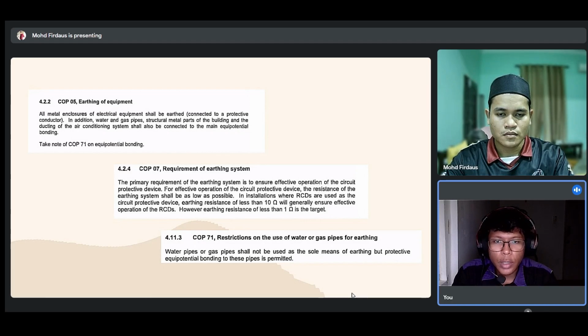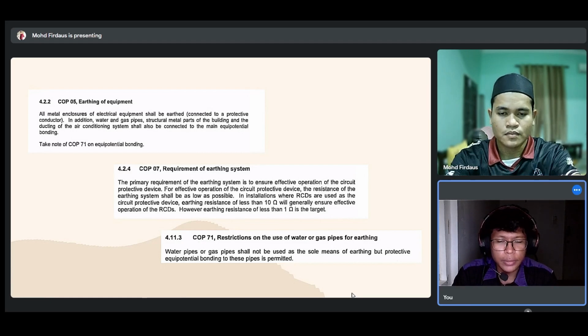In installations where RCDs are used as the circuit protective device, a resistance of less than 10 ohms will generally ensure effective operation of the RCDs. However, an earthing resistance of less than 1 ohm is the target. The lower the earthing resistance, the better.